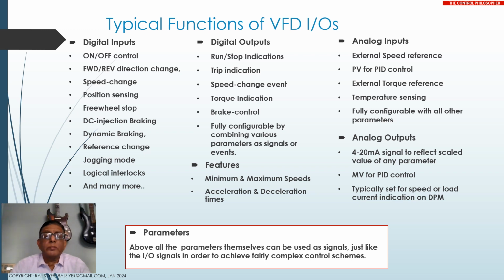Okay, and there is also the possibility of combining all these parameters. Then there are many other features like minimum and maximum speeds. You can place boundaries. Then you can also give them acceleration and deceleration rates, meaning how fast it will accelerate, how slow it will decelerate, and things like that. And then for analog inputs, as I've said, you can use them for external speed reference. It can represent the process variable for PID control. You can use this as an external torque reference. You can use it for temperature sensing, and all these are again fully configurable with all the other parameters. The parameters often refer between themselves. One parameter is used as a reference to another parameter, connected by what Siemens calls a binector connector, BICO, and all these things.